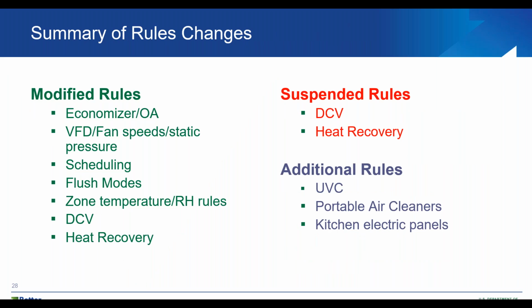So let's kind of summarize the three main things. You're required to modify the rules in FDD, suspend some of them, and provide additional ones. There are a lot of economizer and outside air rules that are already written, and these need to be looked through and modified based on the way you want to be operating the building. The same thing with any kind of air change rates or filters. It's going to be impacting how your system's operating, and the rules need to reflect your current operations, not the previous operations. Some of the rules need to be suspended, like demand control ventilation and heat recovery, anything that's going to be bringing in less outside air, the flip of what we normally would do, those rules need to be suspended. And there'll be additional rules created based on additional pieces of equipment.